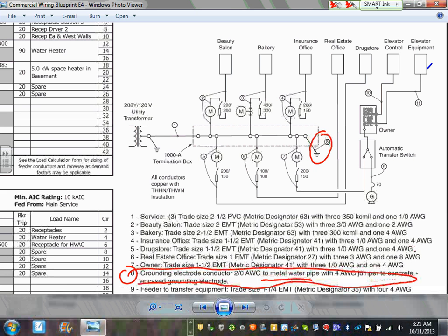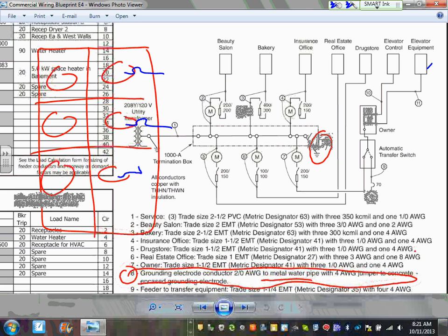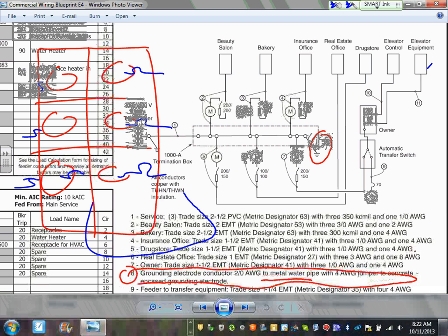So where would you use a system like this, guys? You use a system like this if you have multi-discipline. Another alternative for sizing this project, the way they did it, is to have a meter center, and you have meter center 1, 2, 3, 4, 5, 6, like we did in residential. From the meter center, you come up with a circuit breaker or fuses, and your power will be coming directly from here.